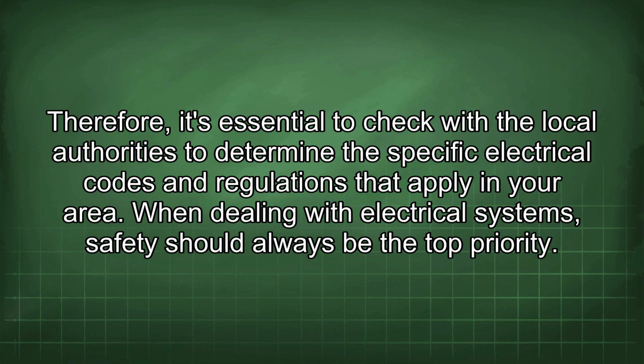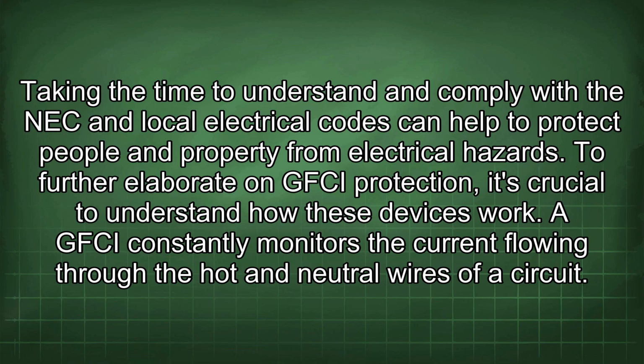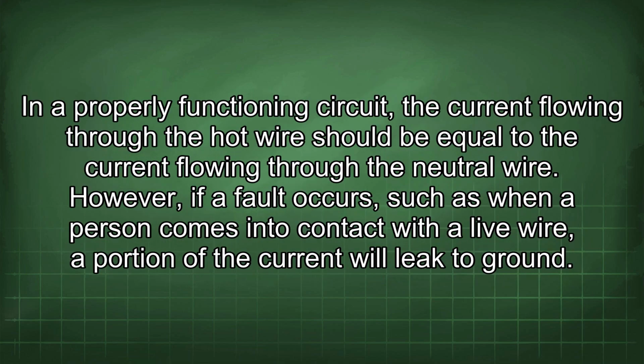When dealing with electrical systems, safety should always be the top priority. Taking the time to understand and comply with the NEC and local electrical codes can help to protect people and property from electrical hazards. To further elaborate on GFCI protection, it's crucial to understand how these devices work. A GFCI constantly monitors the current flowing through the hot and neutral wires of a circuit. In a properly functioning circuit, the current flowing through the hot wire should be equal to the current flowing through the neutral wire. However, if a fault occurs, such as when a person comes into contact with a live wire, a portion of the current will leak to ground.